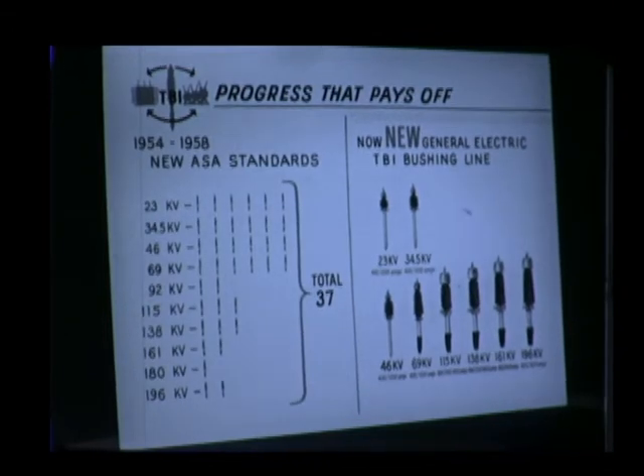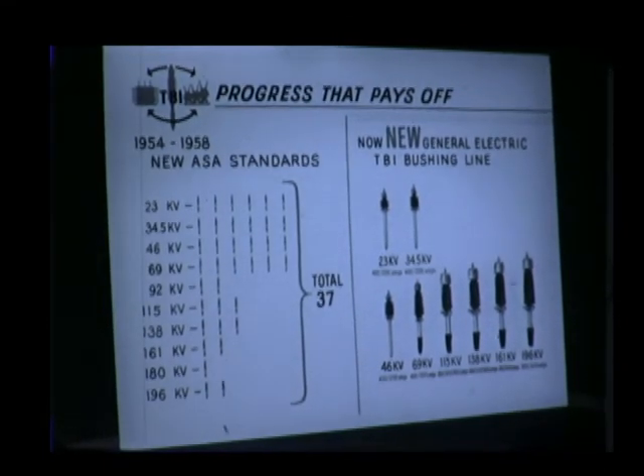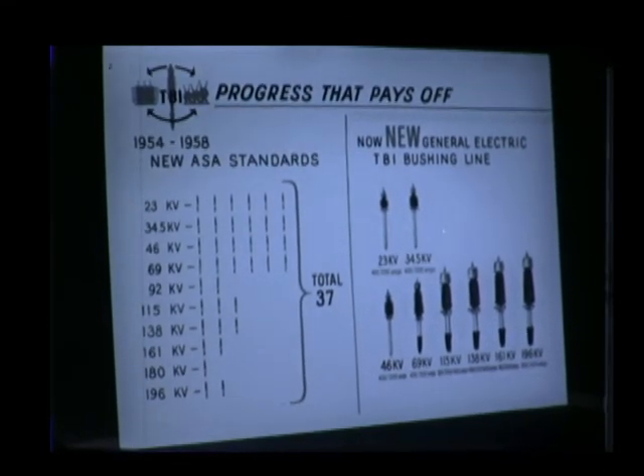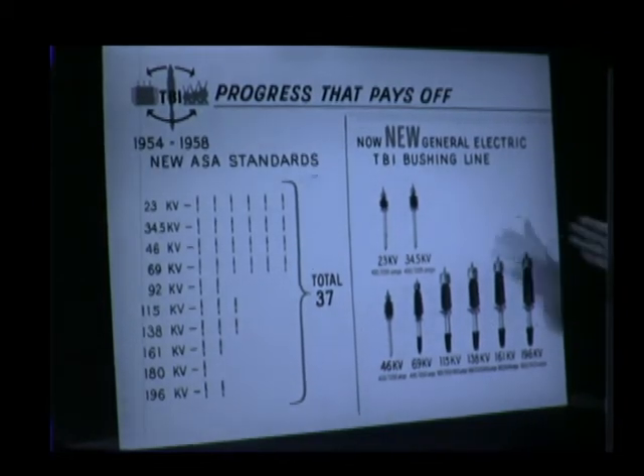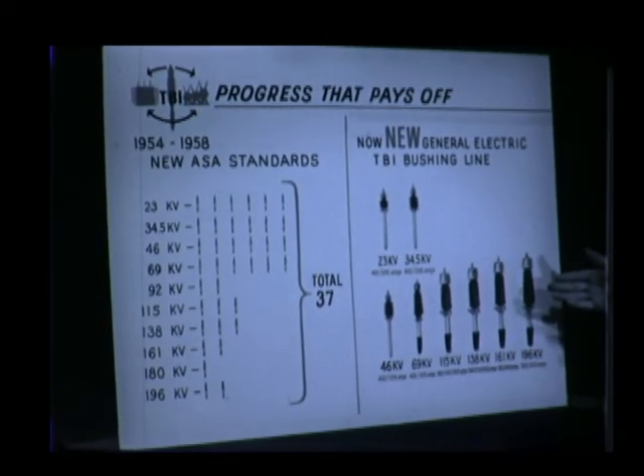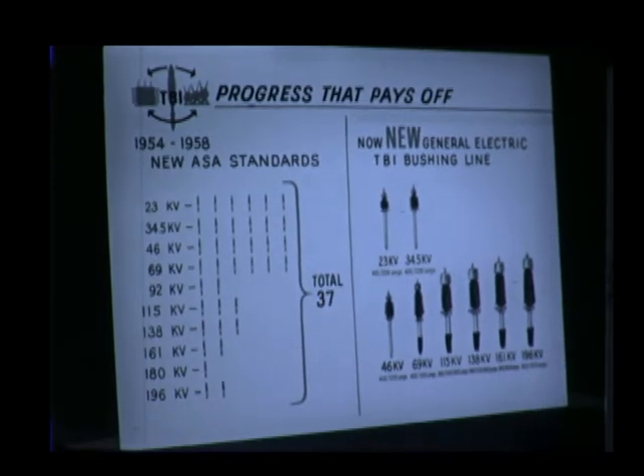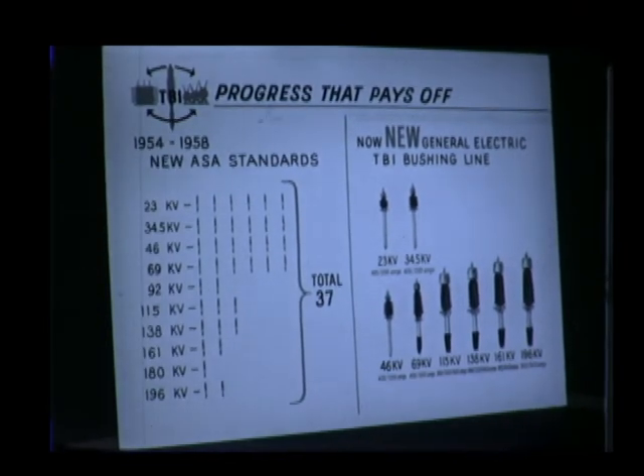Now we're ready to offer a line of bushings which are completely interchangeable between GE power transformers, medium transformers, and oil circuit breakers. They are known as TBI bushings, meaning transformer breaker interchangeable. Just 10 bushings, one for each voltage class, cover the complete range now included in the ASA standards.